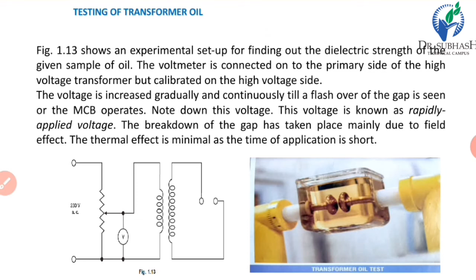Now testing of transformer oil. Figure 1.13 shows an experimental setup for finding out the dielectric strength of the given sample of oil. Here we can see input is 230 volt AC. This is potentiometer, and through the auto transformer supply is given to the primary of the transformer, and high voltage side of the transformer is connected with the spheres. These two are spheres. The voltmeter is connected on the primary side of the high voltage transformer but calibrated on the high voltage side. This one is voltmeter.